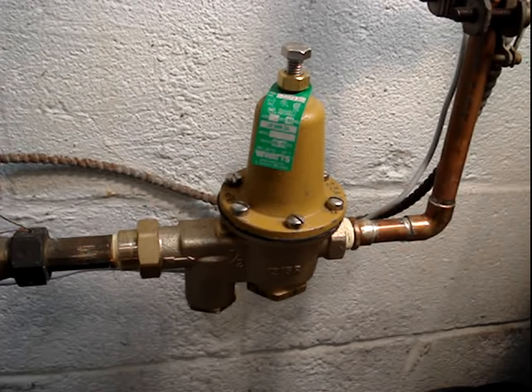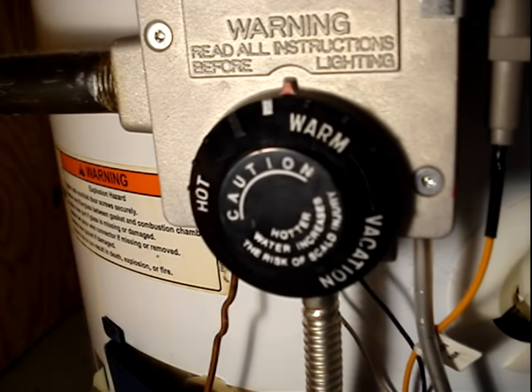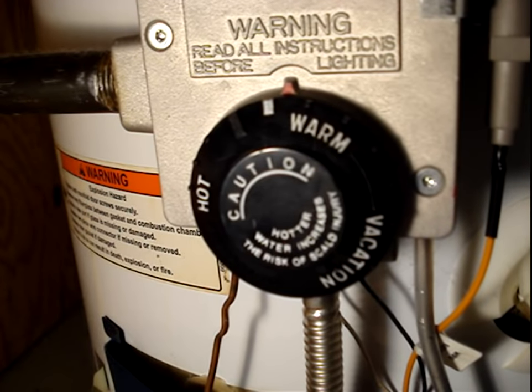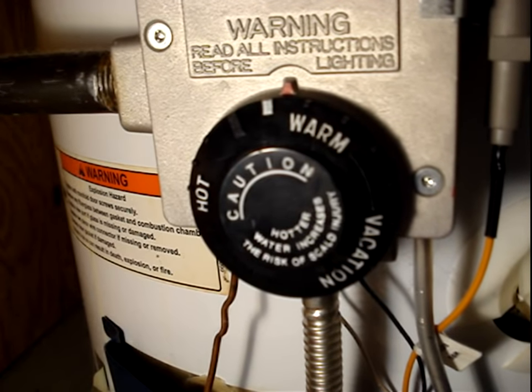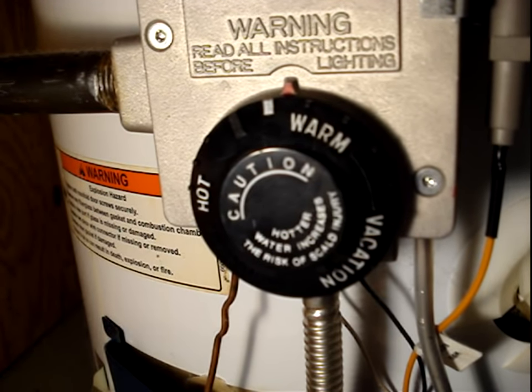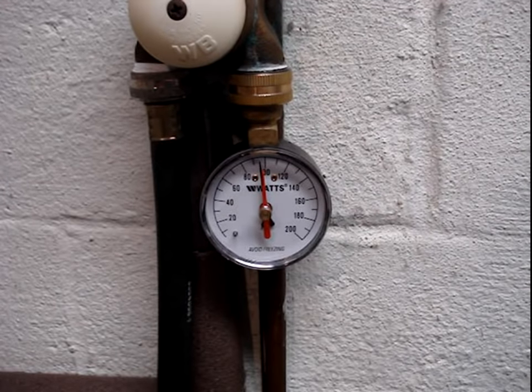I'll do a test to find out if thermal expansion is causing the T and P valve to open. I'll increase the setting on the water heater until it starts to heat water. You could also open a hot water tap for maybe five, six, seven minutes to cause this to happen.